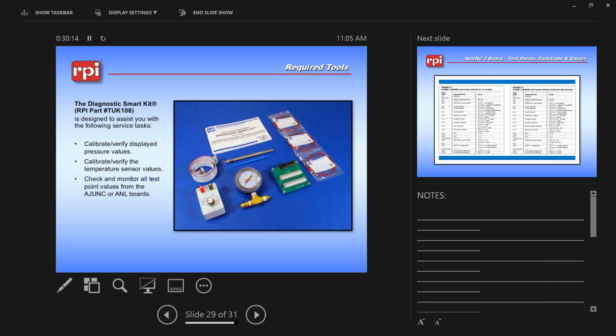What you're going to want to do from there is shut the unit down. You're going to disconnect just the test box. You're not going to disconnect your test point board. Once you've disconnected it, plug back in your actual temp sensor, power the unit up, leave your meter at pins 1 and 4. It should still be set to 500 millivolts. And you're going to run a cycle. Doesn't matter which one, you can choose unwrap, it's the fastest.